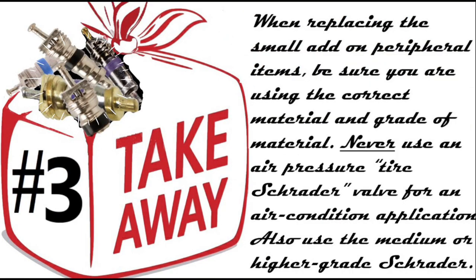Number three: when replacing the small add-on peripheral items, be sure you are using the correct material and grade of material. Never use an air pressure tire Schrader valve for an air conditioning application — you'll see that all too many times. Also, use the medium or higher grade Schrader.